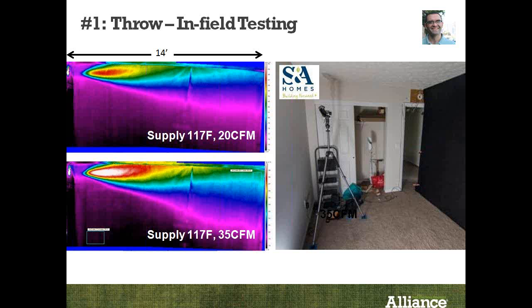shows a piece of black felt hanging in front of the air diffuser, and basically you ran this in heating mode. Yep. Yeah, we ran this in both heating and cooling mode, and basically we turned the system on in fan-only mode for maybe a 10-minute period to equalize the temperature throughout the room, and then we kicked it on to one of several different air flow rates in both heating and cooling mode, and we used an infrared camera there, and we're able to take pictures and see the progression over time as to how well those particular flow rates were able to get air into the room.